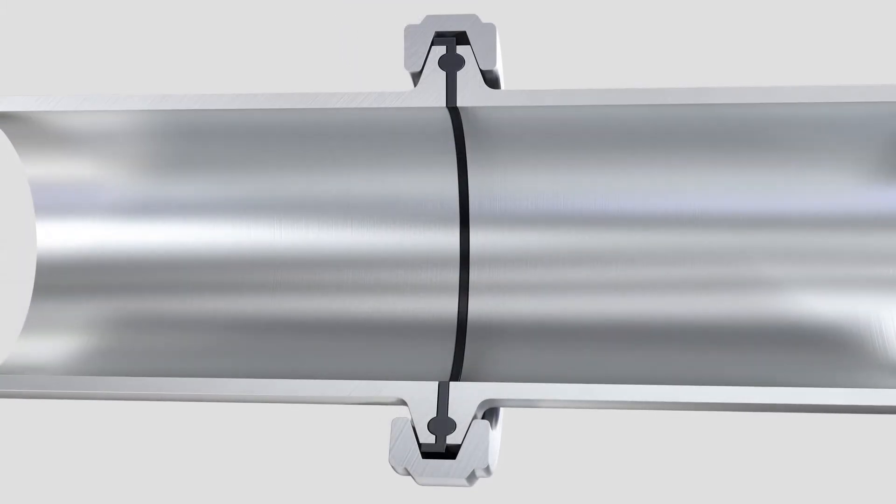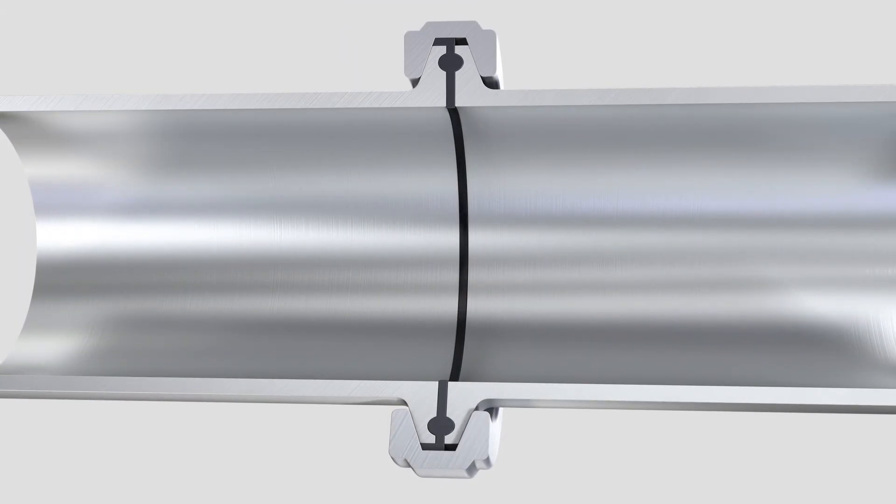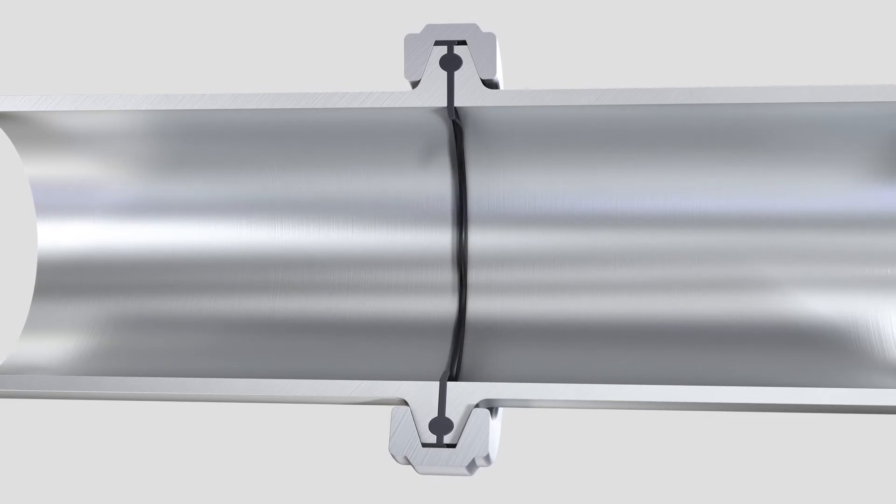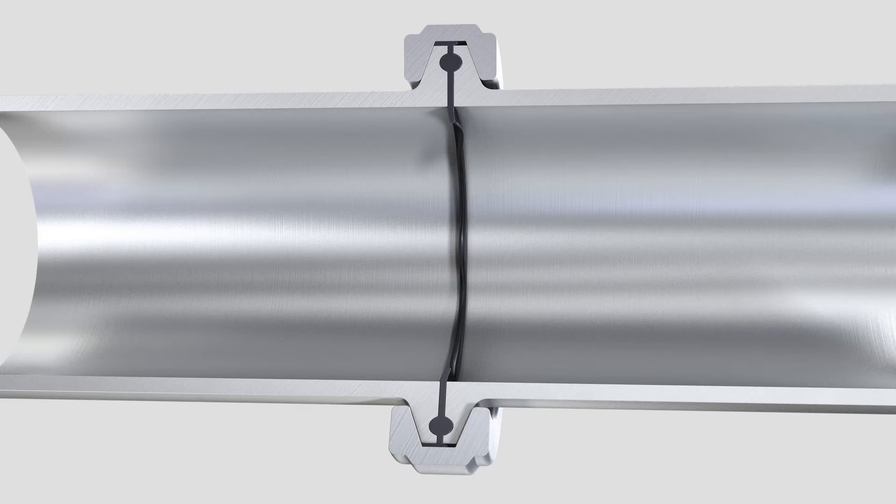If too much pressure is applied, the sealing lip might protrude into the inside of the pipe. This creates deposit areas for germs and other contaminants so that the connection is no longer hygienic.